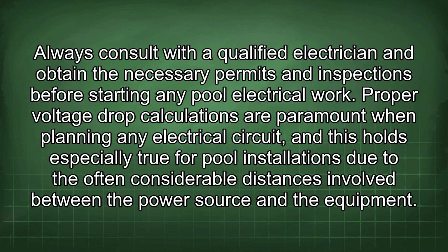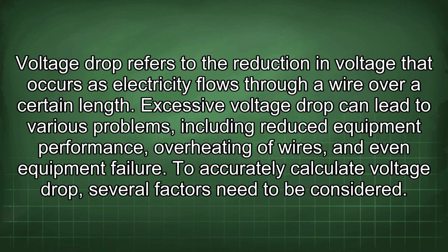Proper voltage drop calculations are paramount when planning any electrical circuit, and this holds especially true for pool installations due to the often considerable distances involved between the power source and the equipment. Voltage drop refers to the reduction in voltage that occurs as electricity flows through a wire over a certain length. Excessive voltage drop can lead to various problems, including reduced equipment performance, overheating of wires, and even equipment failure.